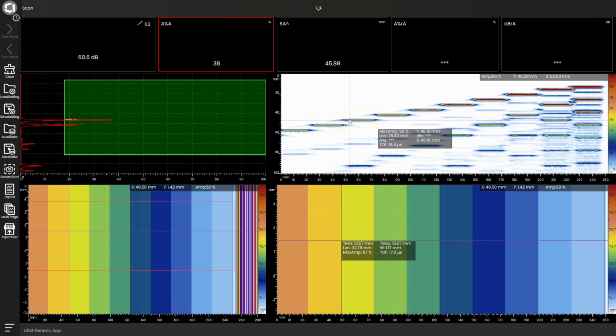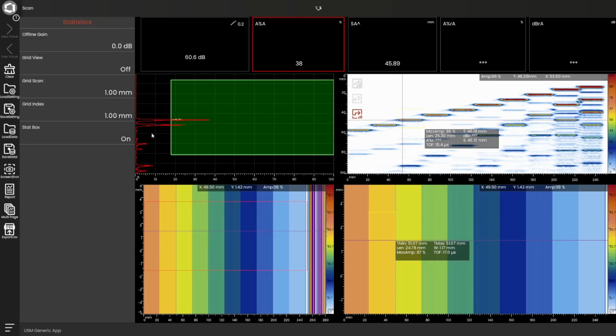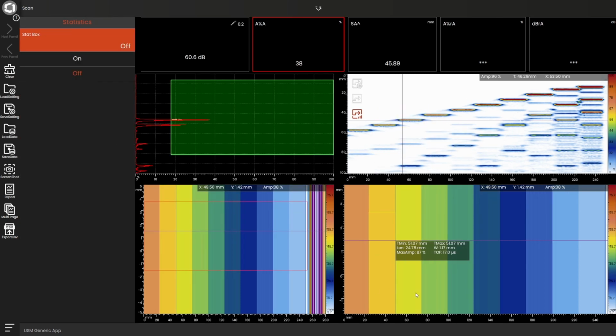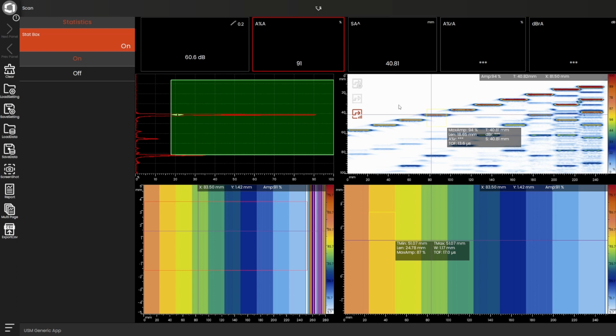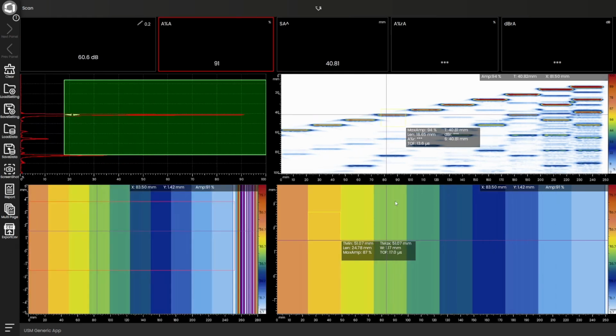On the B-scan, the cursor is going to snap to the highest amplitude anywhere in the box. So we get a good look at the A-scan that goes with the highest amplitude that we saw along the length. And again, we get various pieces of amplitude information, time of flight, that sort of data in that box as well. If we want to make those boxes go away, that's on the display menu. Turn the stat box off, and we can hide those, but they will come back on when we draw a new box. All right, so that's some of the analysis features.